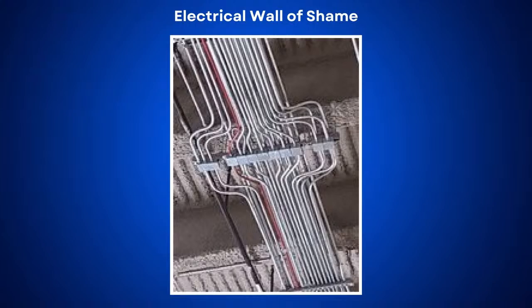Yeah, that's ugly looking. The thing is, you're basically exceeding your 360, in my opinion. I don't even have to see any more of the run. I go in there, I see that, I'm like, you're exceeding 360. I'm gonna go find it. Because if you even do just 2 back-to-back 90s to get around something, to me, that's why those outside back-to-backs are hideous. Those outside ones, you already got 180 degrees, and these look like pretty long runs up in the thing. So I'm willing to bet you're probably over 360.